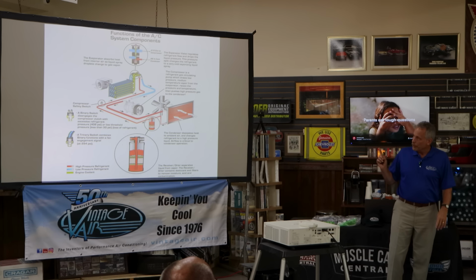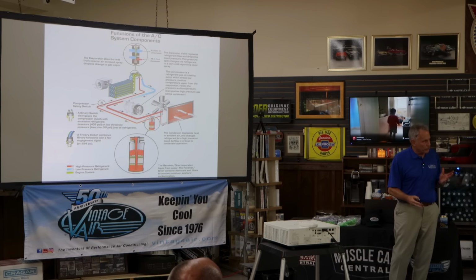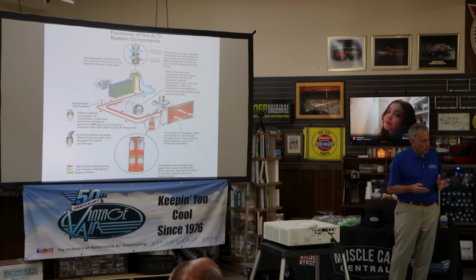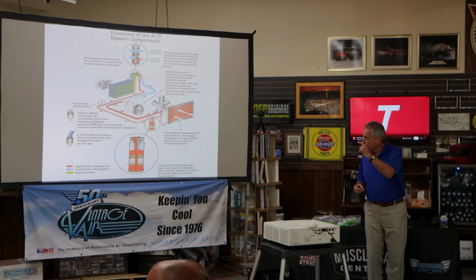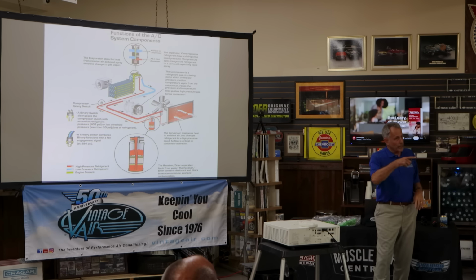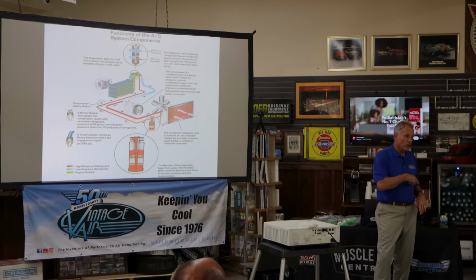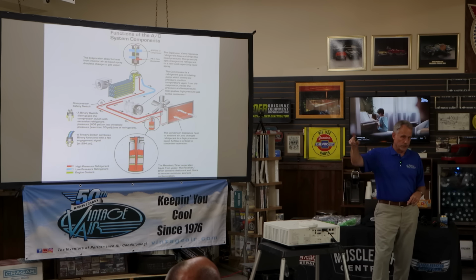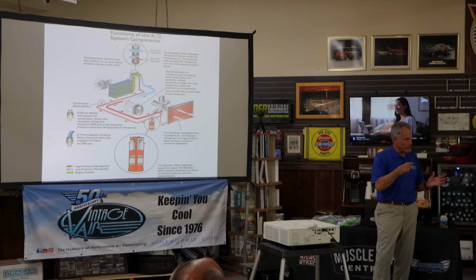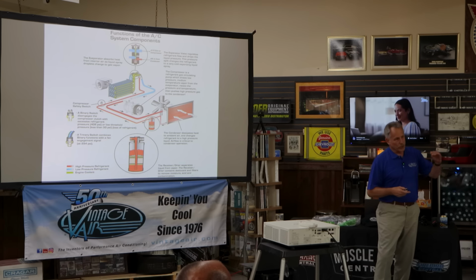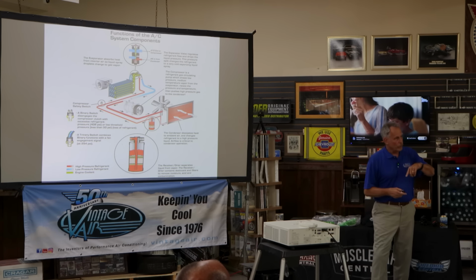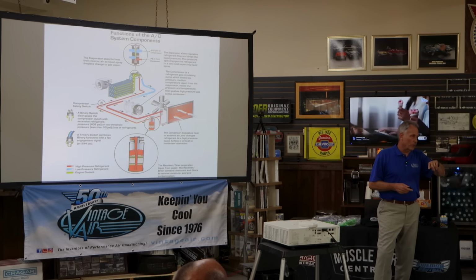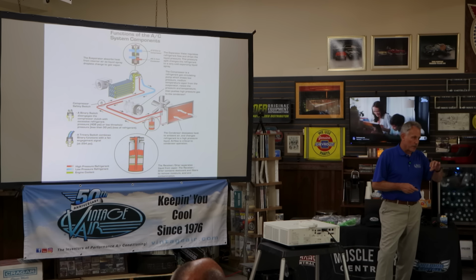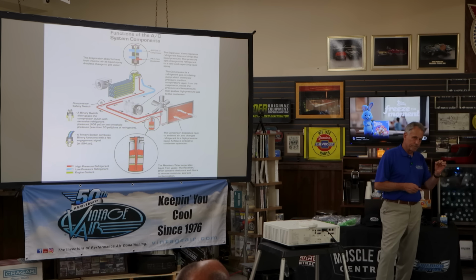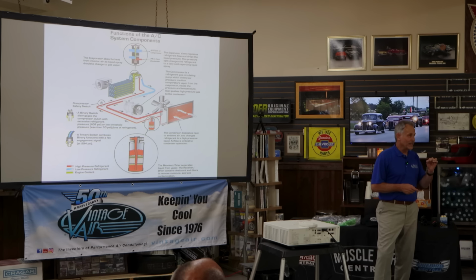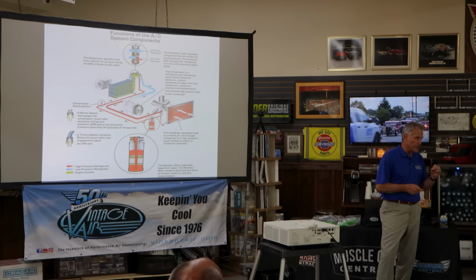The problem with 134A, not the problem, but one of the chemical differences of it, is the molecules are so much smaller that in addition to refrigerant circulating through your system, we also have refrigerant oil circulating through the system. From the compressor through the system, it lubricates other parts of the system. It circulates in suspension with the refrigerant. The molecules of 134A are so small that the bubbles you see are actually oil bubbles. They haven't completely dissolved, they're just there.